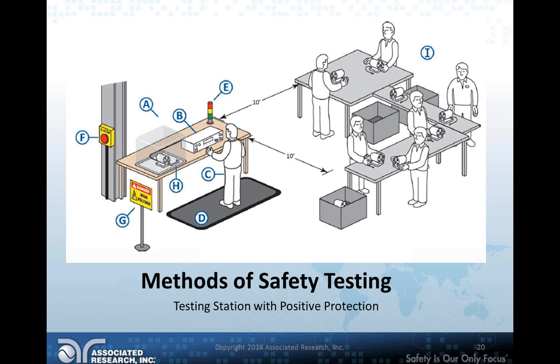Yes, the operator knows there's danger high voltage, but somebody walking by or working in the near area, or a visitor walking by, for example, might not know what a high pot testing station is. So it's always a good idea to have high voltage signs up well away from the testing area to let people know not to walk in an area. Another way I've seen it done is tape on the ground, yellow or red tape that says danger high voltage that encloses the entire testing area. And then, of course, there's an e-stop switch in that entire station. E-stop switches are usually wired up to station power, not just the high pot tester, the whole station. So if there's a problem, somebody's getting shocked, somebody can walk by, slap that e-stop, and it cuts off power to the entire testing station.